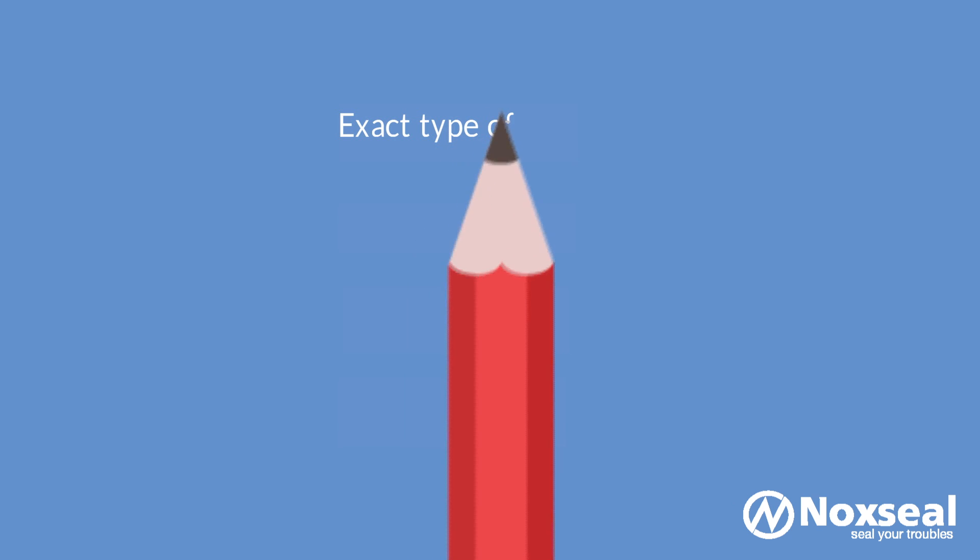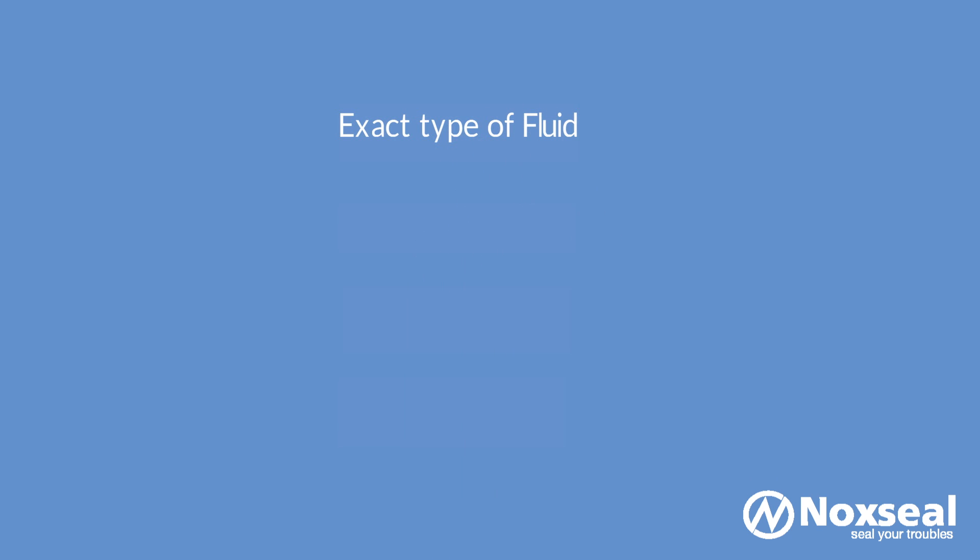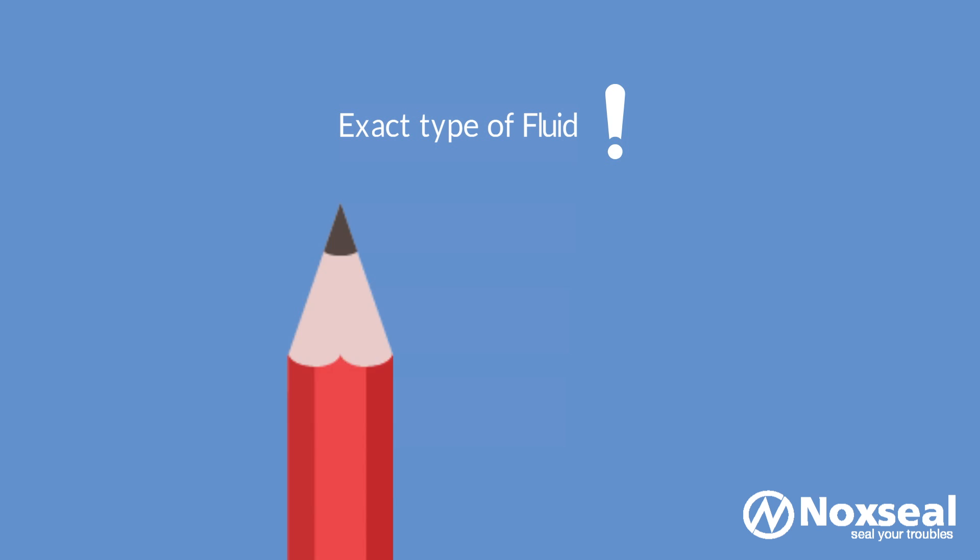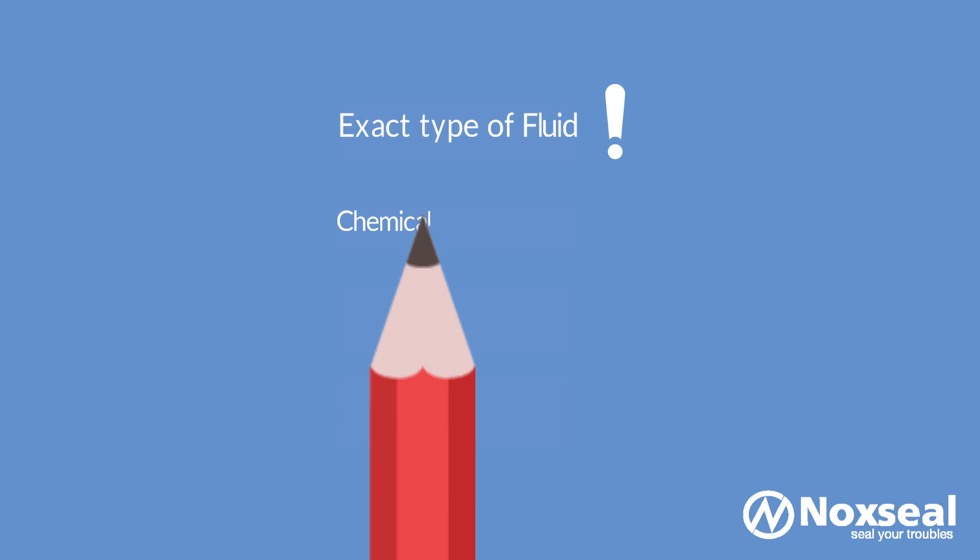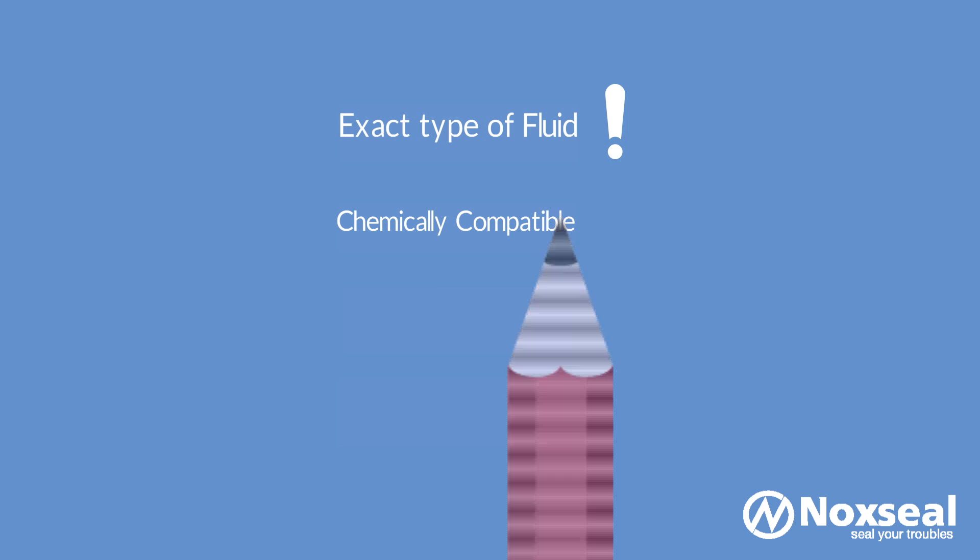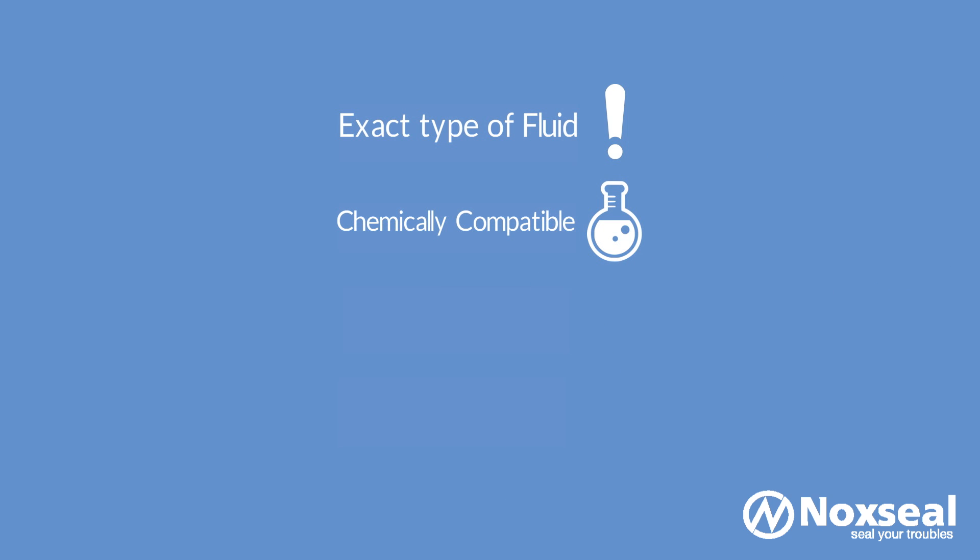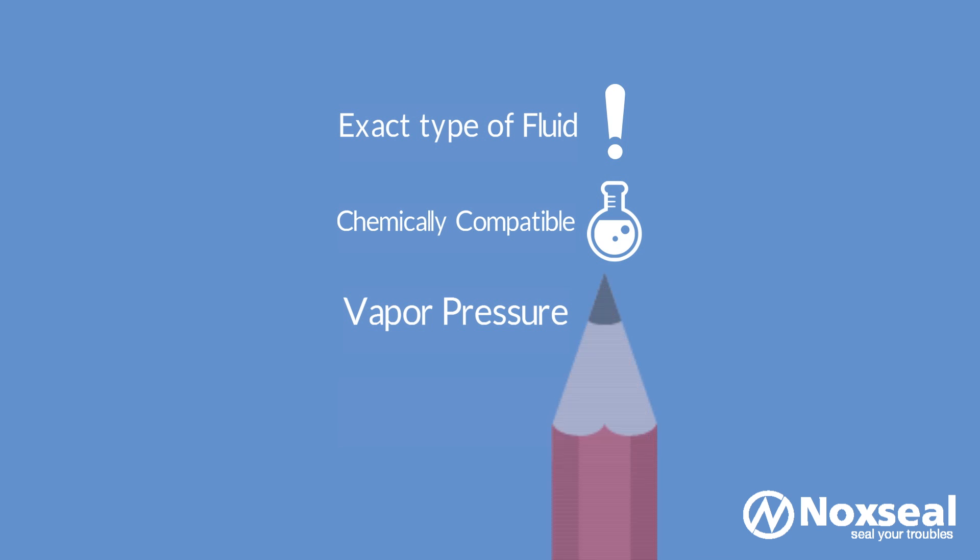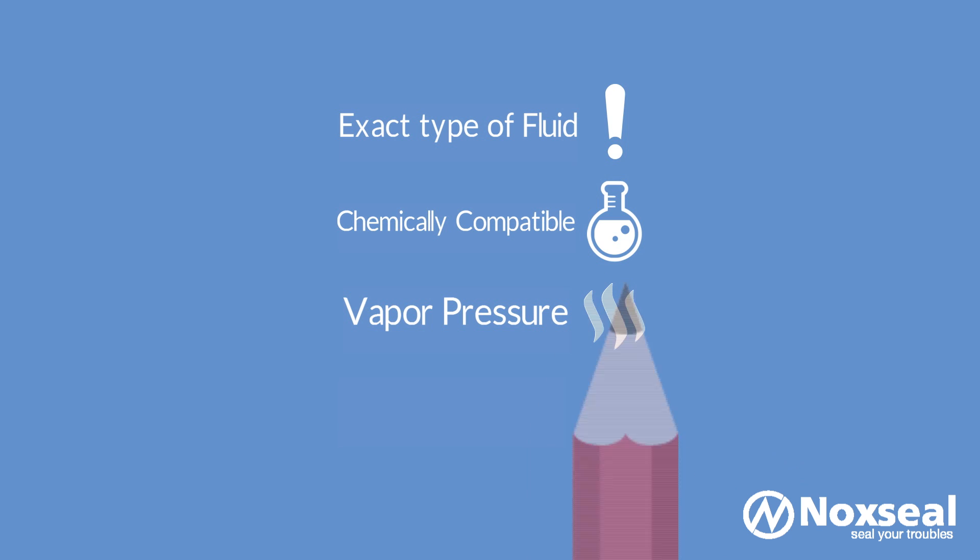Step 2: Liquid. Identifying the exact type of liquid or fluid to be pumped is foremost in the seal selection process. The material of the seal must be able to withstand the fluid being processed. There might be seal failure if the seal material is not chemically compatible with the fluid. In addition, you should also know the liquid's vapor pressure to ensure the fluid being sealed remains in a liquid state as it flows across the sealing faces.